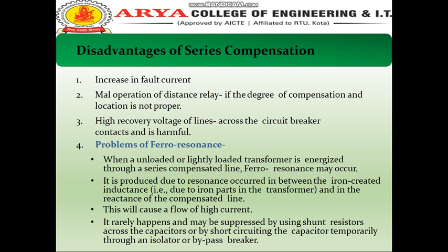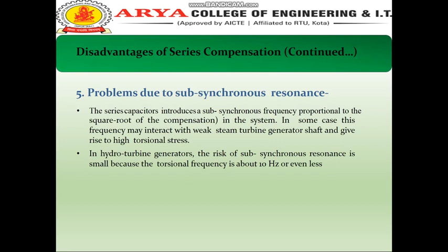The problem due to subsynchronous resonance. The series capacitor introduces a subsynchronous frequency proportional to the square root of the compensation in the system. In some cases, this frequency may interact with a weak steam turbine generator shaft and give rise to high torsional stress. In hydro turbine generators, the risk of subsynchronous resonance is small because the torsional frequency is about 10 Hz or even less.